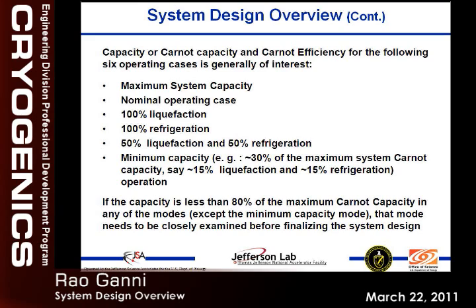And if you look at it at the front of the design level, the implications are not that strong on the cost. The question is how they are arranged, and people can take advantage in the components they are using if it is not specified. Like I said, we had one of the pipes small in the SNS refrigerator on the cold end. It's just a piece of pipe. It's limiting the 4K refrigeration, because in the specification we did not specify that mode of operation.